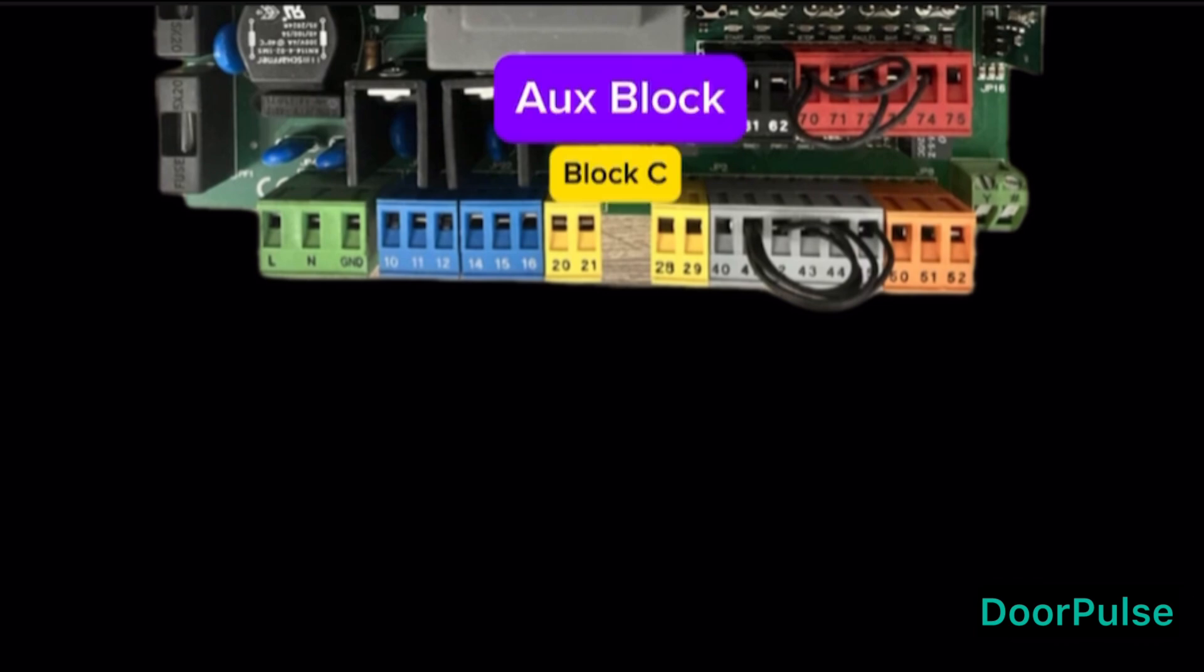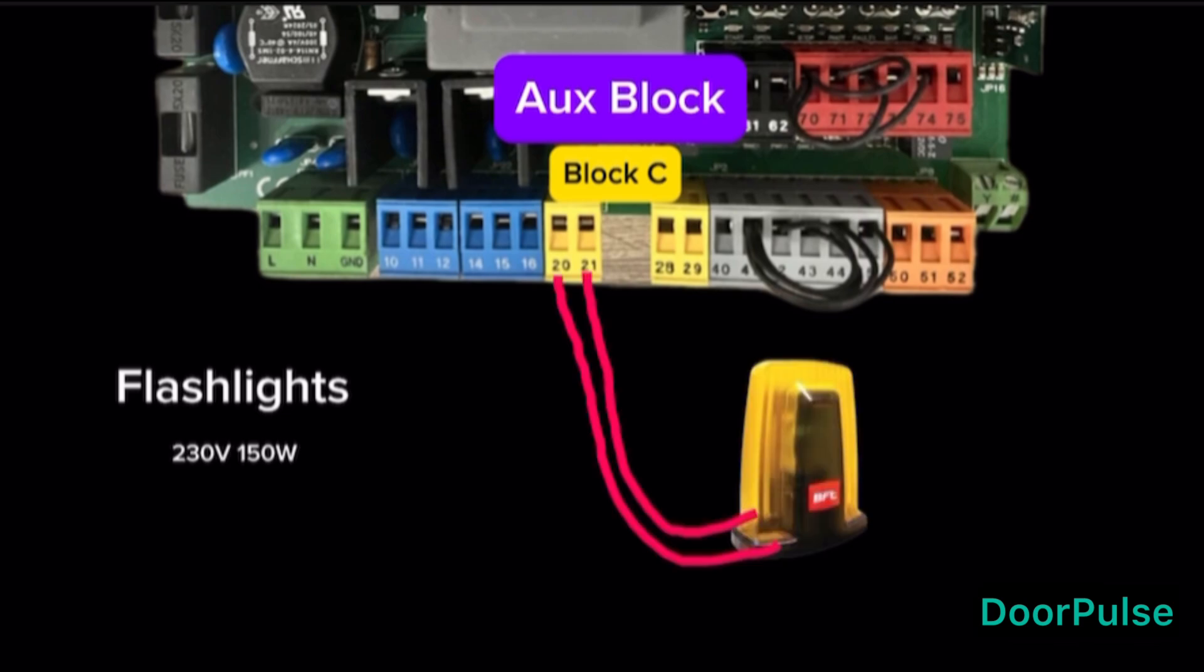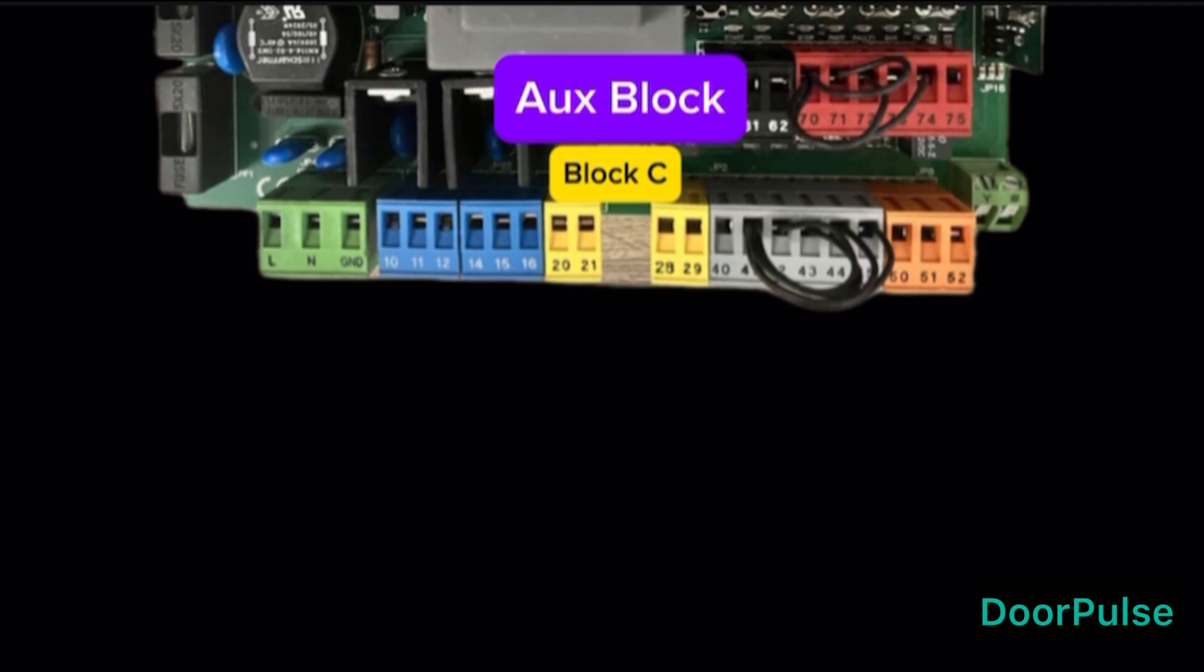Block C, AUX Block. Terminals 20, 21, flashlights block. Connect a flashlamp rating is 230 volt and 150 watts max. Terminals 28, 29, electric lock block.